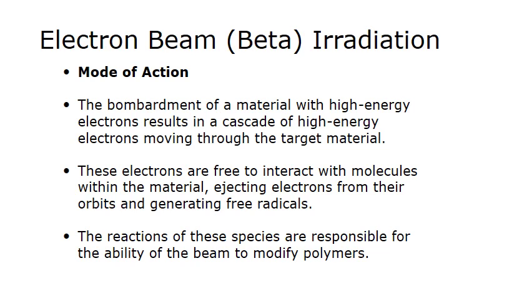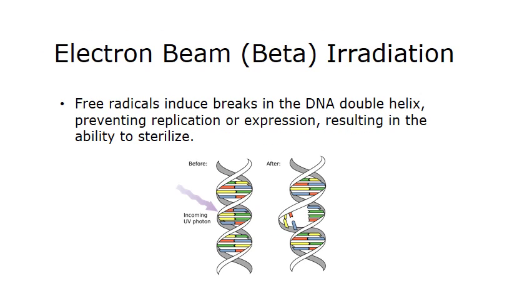With electron beam irradiation, the material is bombarded with high energy electrons, resulting in a cascade of high energy electrons moving through the target material. These electrons interact with molecules within the material, ejecting electrons from their orbits and generating free radicals. It is these free radicals that are responsible for sterilization of the medical device. Free radicals can kill any microbes present on the device, however they also have the ability to modify the polymer itself.